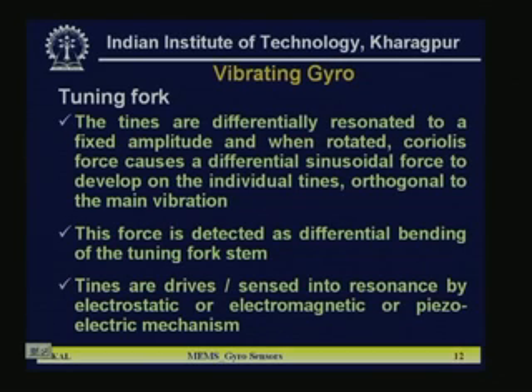In a tuning fork gyro, the tines are differentially resonated to a fixed amplitude. When rotated, the Coriolis force causes a differential sinusoidal force to develop on the individual tines orthogonal to the main vibration. This force is detected as differential bending of the tuning fork stem. I will discuss this with a diagram in the next slide. The tines are driven and sensed into resonance by electrostatic, electromagnetic or piezoelectric mechanisms.